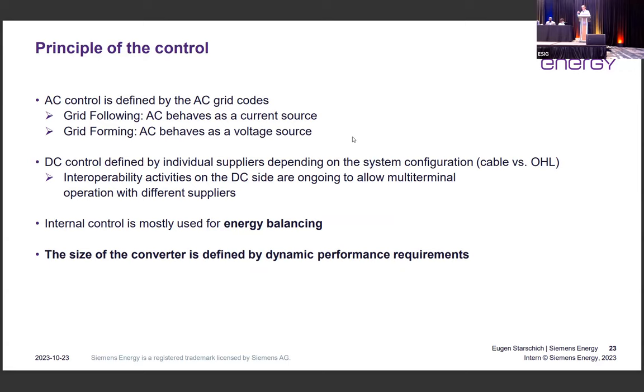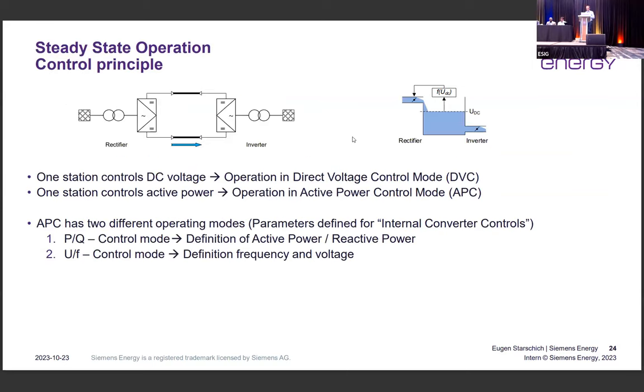Looking at the size of the converter, as mentioned before, the size is mostly defined by the capacitors, and capacitor means energy storage. Looking at the requirements that we see on the market, the dynamic performance requirement is what defines the size of the converter. So it's not only the steady state design. We always ask the customers: the steady state design is fine, but what are the dynamic requirements? Because the dynamic requirements are the key factor for the sizing of the converter.